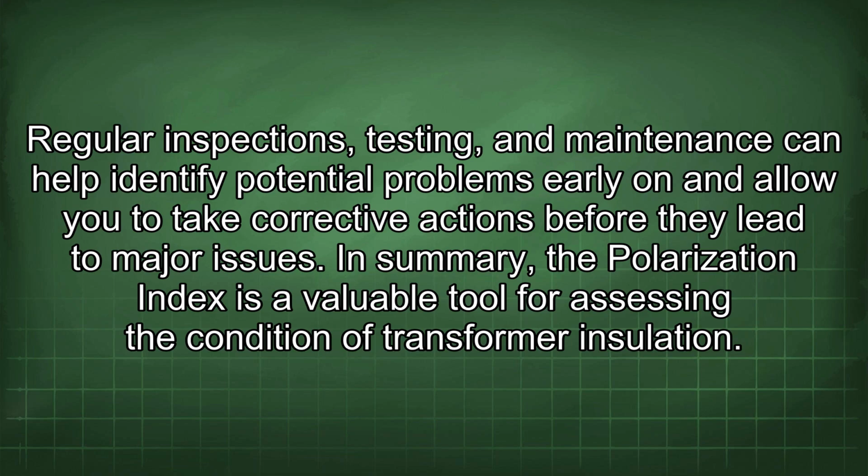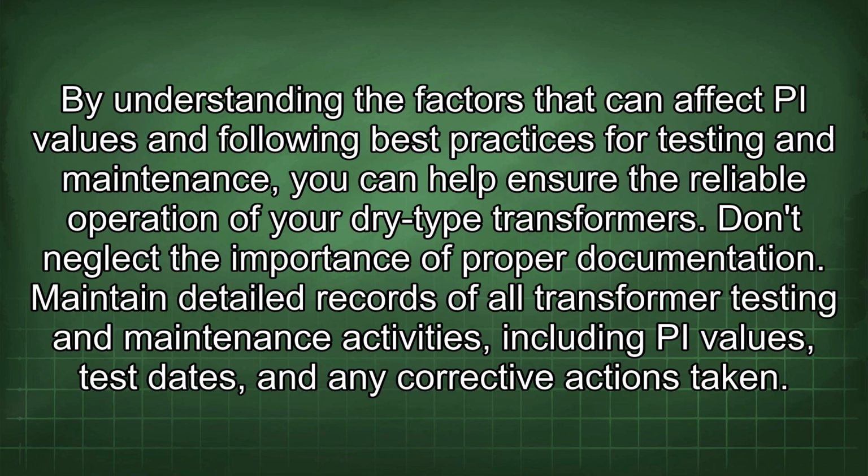In summary, the Polarization Index is a valuable tool for assessing the condition of transformer insulation. By understanding the factors that can affect PI values and following best practices for testing and maintenance, you can help ensure the reliable operation of your dry-type transformers.